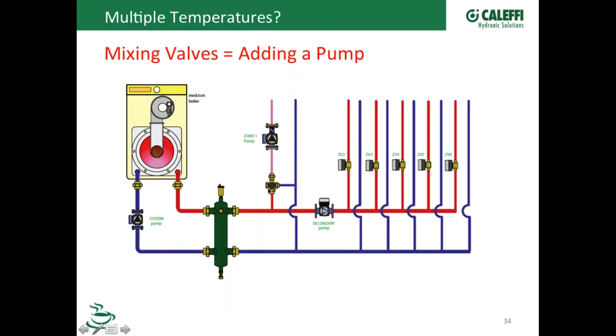We get too many calls, in my opinion, about guys that install a thermostatic mixing valve and they want to add a radiant zone that's maybe running 120 or 130 versus their cast iron radiators or copper fin tube, and they're trying to use a single pump to operate both of these devices or both of these temperatures, and mixing valves, you can't pump into the hot inlet.